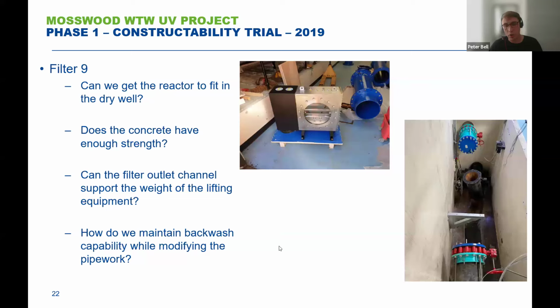What we found when we were going the long way around the channel is there was a lot of hydraulic losses introduced due to a pipe bridge at the bottom. And that reduced the flow down to 350 litres a second, which wasn't suitable for the backwash that we needed and introduced too much of a water quality risk. So we had to work out how we would then maintain this backwash capability whilst we didn't have the ring main available. Now on this one specifically, for number 9, because of the amount of filters, it only actually affected filter number 11. So it was much easier to manage that filter because we could stagger the filter washes, which are approximately every 4 to 6 hours per filter.